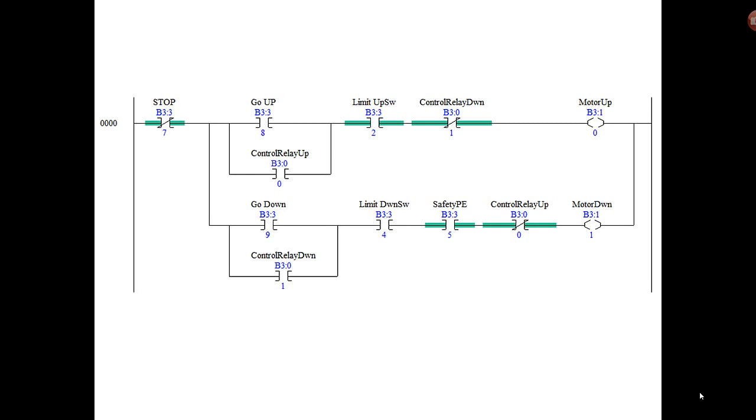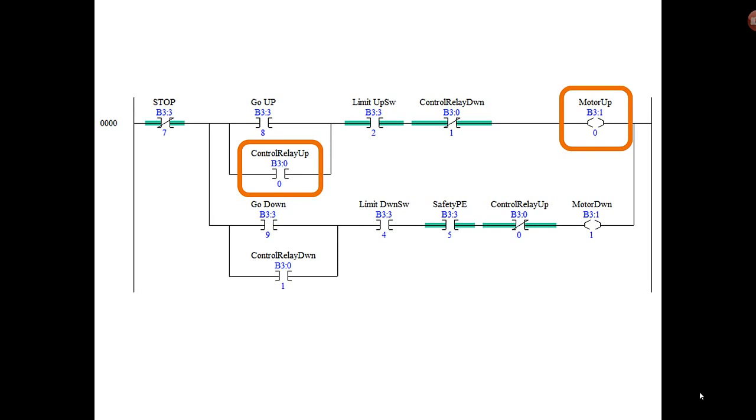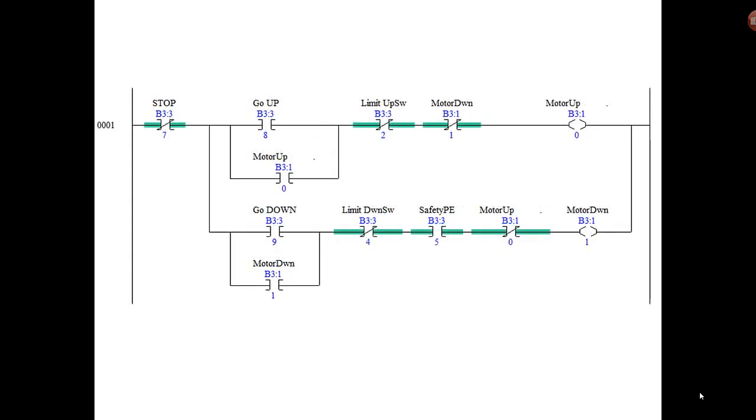So why not just move it into one rung? You have a single stop bit that clears the command to motor up or motor down. Now notice that this used to be control relay up. Well, this is still control relay up. That's a problem, because remember that the instruction that is in parallel with the go up button has to seal that in, because you're only going to toggle the go up bit like a momentary push button. You push and let go and you expect the motor to keep running in the up direction.